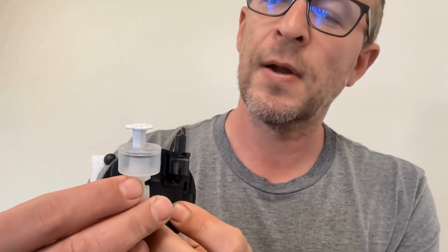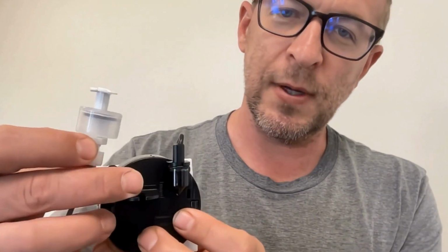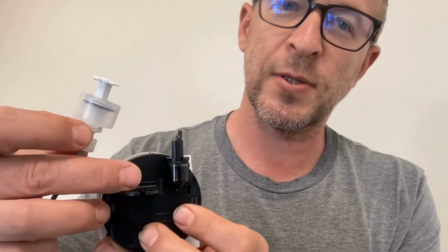Float switch always goes on this mount. This is important because in this position the magnet field is canceled. And I also want to point out that the inside and outside magnet are different in size. One is about 2.5 inches in diameter, one's about 2 inches. They do not line up in the center, they line up at the bottom. Again, that is specifically to shield the float switch from the magnetic field because it is a magnetic switch.